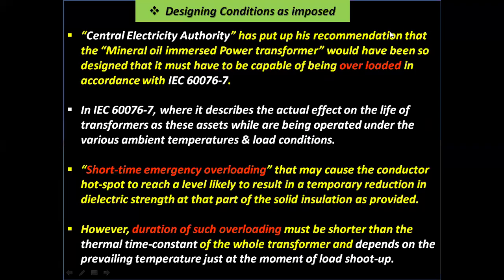Now let's start with the design conditions imposed for the insulation part. The Central Electricity Authority has recommended that mineral oil immersed power transformers be designed so that they are capable of being overloaded in accordance with IEC 60076-7.